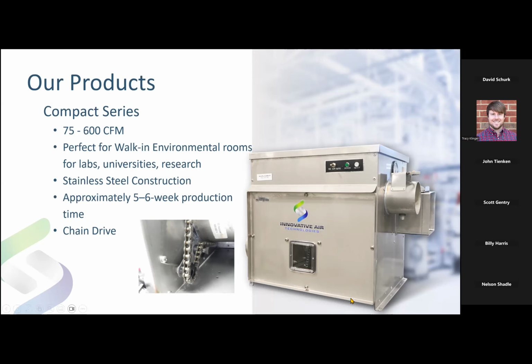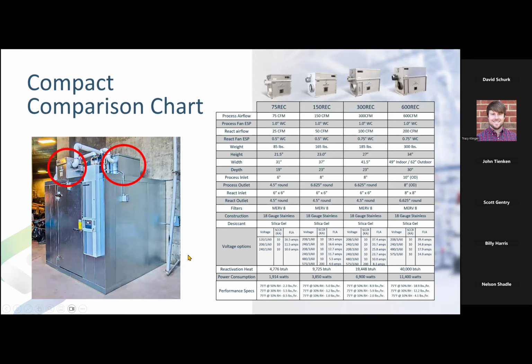This unit comes in stainless steel. It can be installed indoors. It can be installed outdoors. It comes with the process fans. It comes with the regeneration fans. It comes with the filters that are required. And it comes with an electric heater. So it's totally self-contained. All of our units are driven by a chain. You see the chain drive and motor rotor assembly here. It's a little more robust on the bigger units with the bigger wheels, but the point is no belts to slip or break. We're very proud of that. We build a very high quality product that's built to last and be durable.